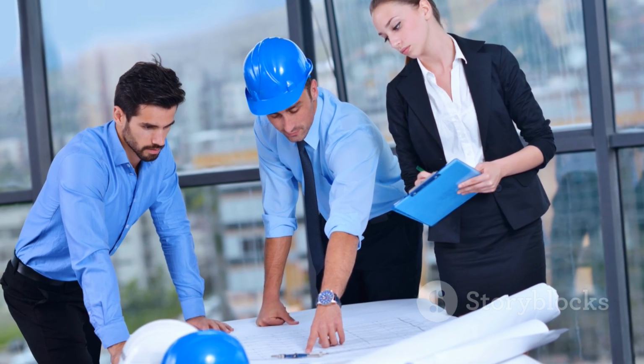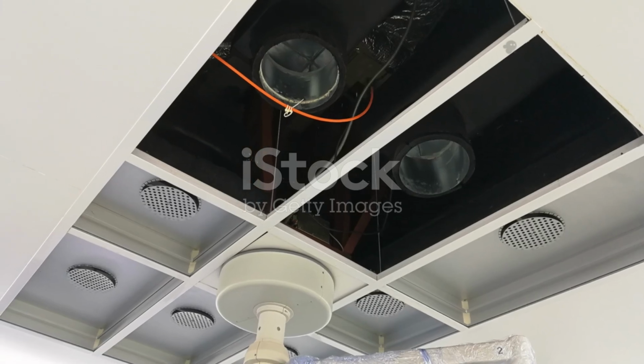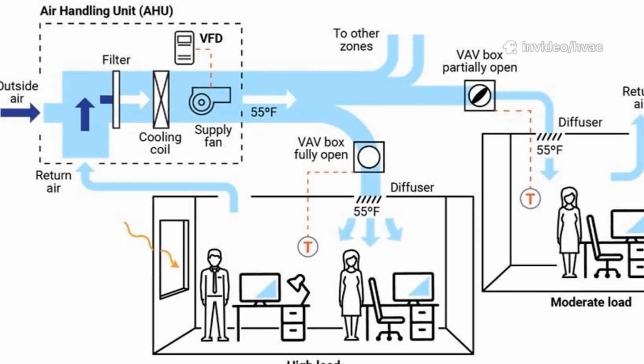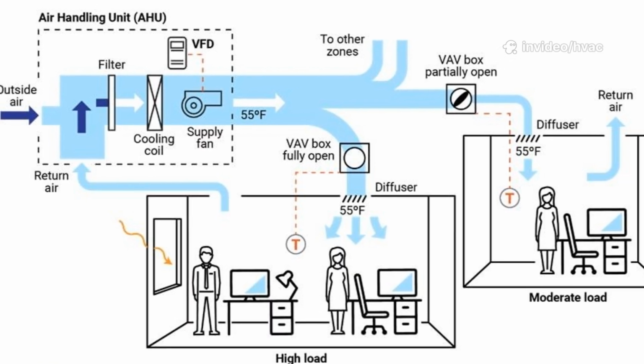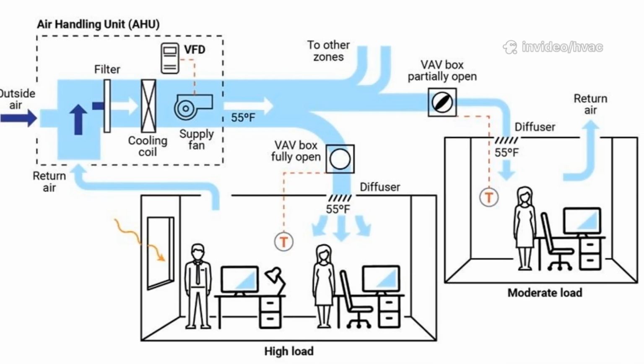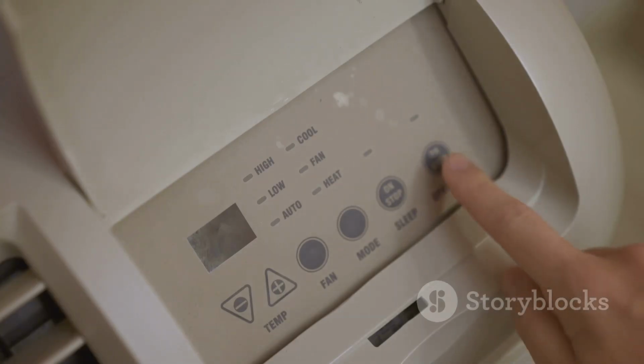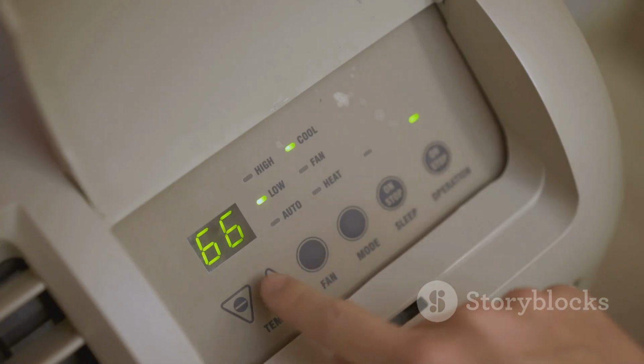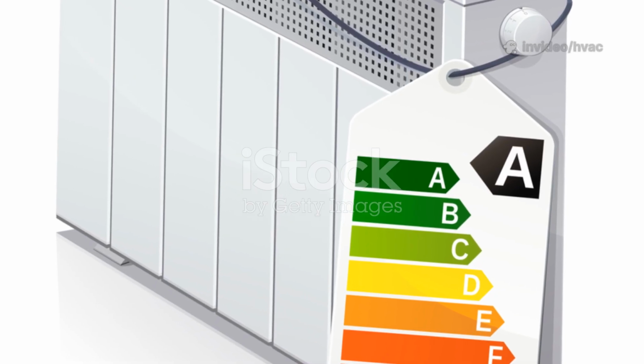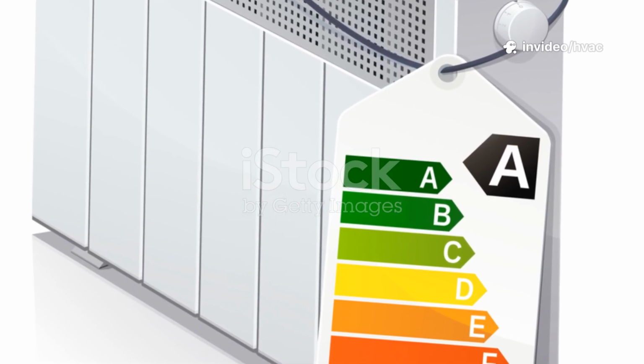What's the payoff? VAV cooling-only systems deliver more than just comfort. Each zone gets its own set point, eliminating hot and cold spots and boosting productivity. The real star is energy savings. Slowing the fan just 20% can cut energy use by nearly half. No more wasteful reheating, and lower electricity bills pay for the system in just a few years.